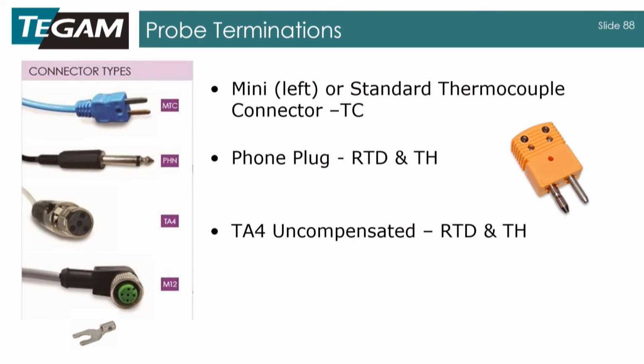And one thing to note, as Adam was saying earlier, is that you can have a 2, 3, or 4 wire measurement RTD device. In my experience, every type of those uses this same type of connector. They just will leave out certain pins. So it's important to know what type of RTD you're using and what pins they use, and that they match up with the instrument that you're plugging into. These are all documented in spec sheets and things like that.